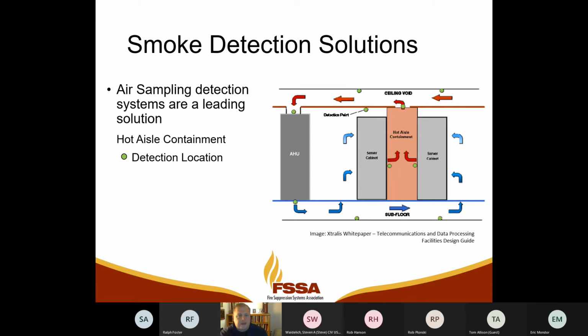That's how you set it up. That's basically the method that Xtralis recommends now, and I hate to give away too much information, but that's the way that AT&T wants their detectors set up, and that's basically what Xtralis says for everybody now. You take the target hole obscuration divided by the number of holes, and that's what you set the alarm threshold at in the detector.